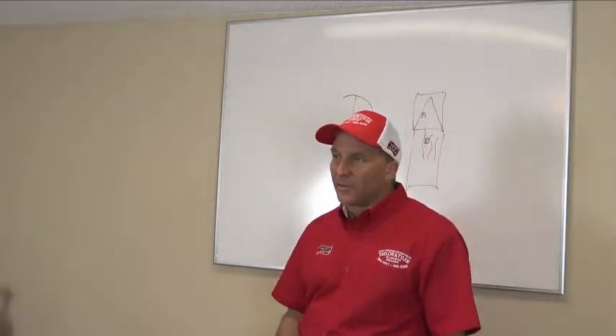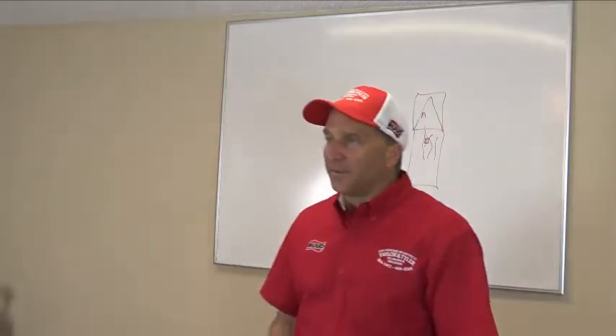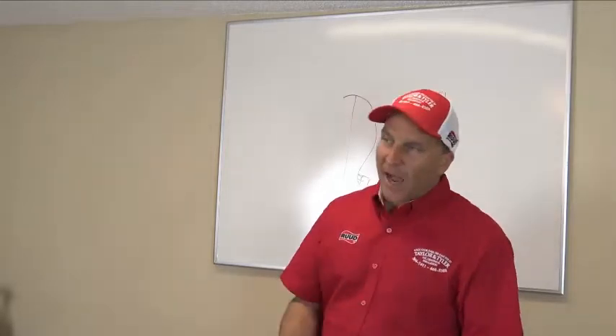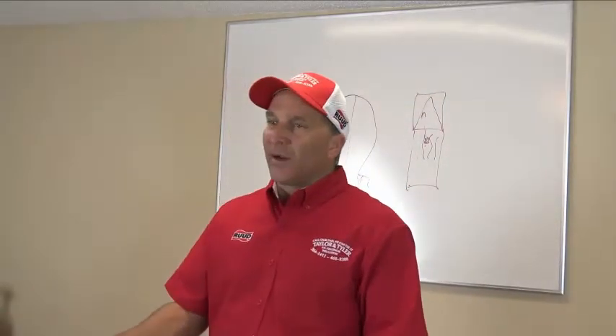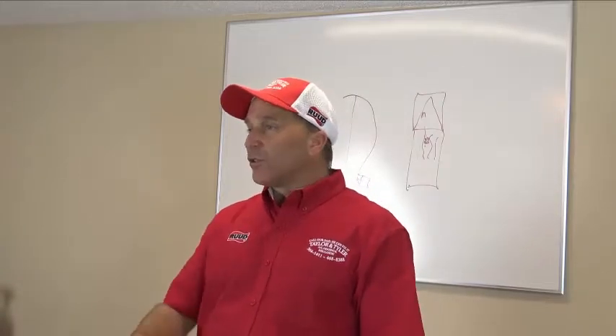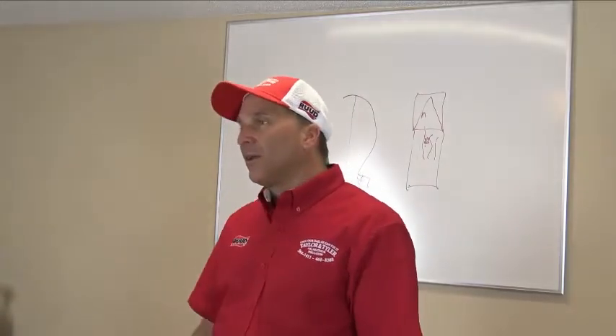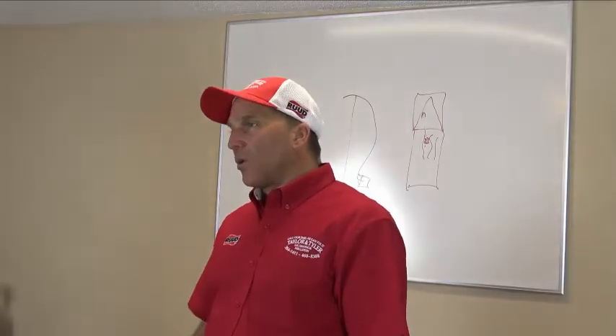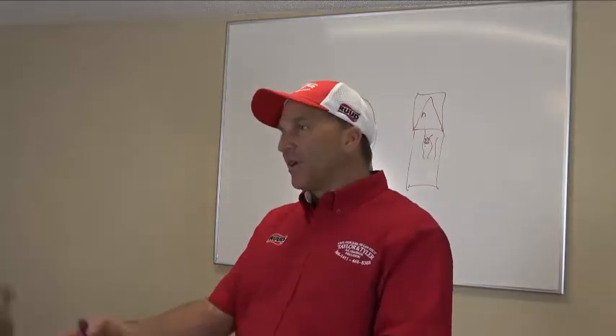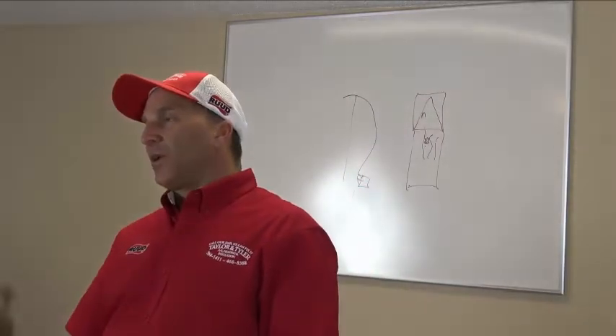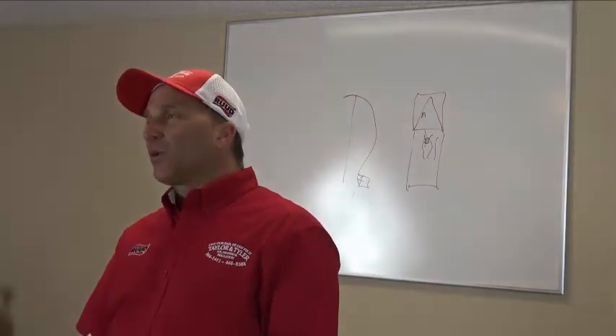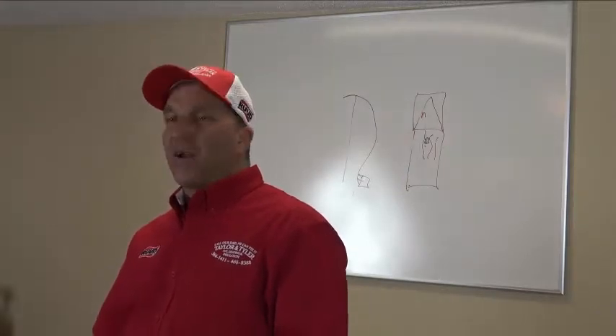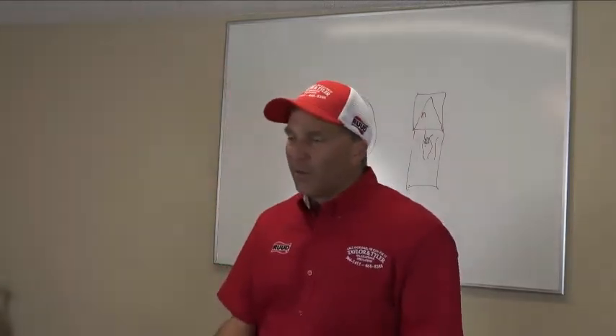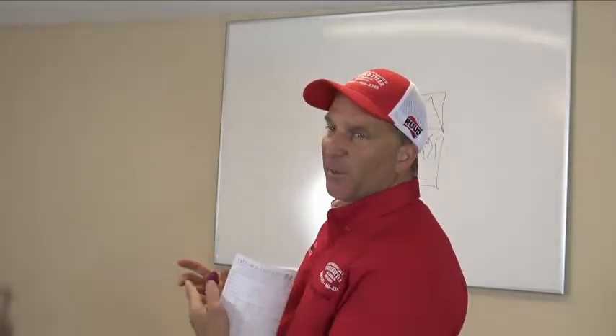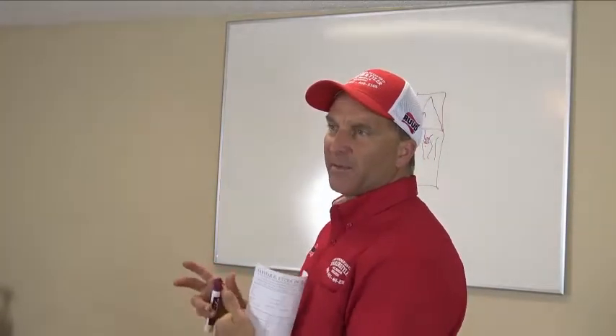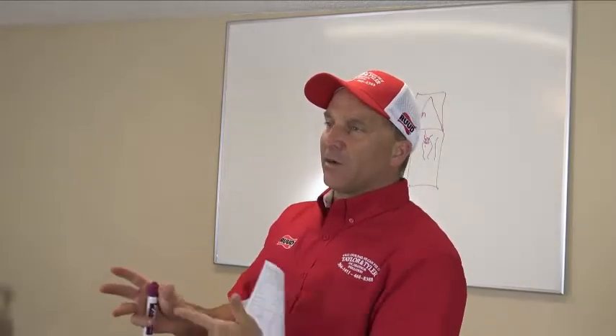Ryan, I'm going to your house and you've got two little kids and a wife. And I go, Ryan, I went ahead and checked your supply plenum and your ductwork up there. Your system's working fine. Your pressures, your temperatures, your electrical, everything's working fine. But while I was up there, I went ahead and checked your ductwork. I looked at your supply plenum, I pulled the cap off of it, and I took some pictures of the inside of it. Because a lot of times we build a lot of mold and mildew up inside these systems. And I don't know if this is of any interest to you whatsoever, but here are the pictures that I took inside your supply plenum. You see all that mold growth up inside that system? Did you want me to take care of this, or did you want to leave that in your house?